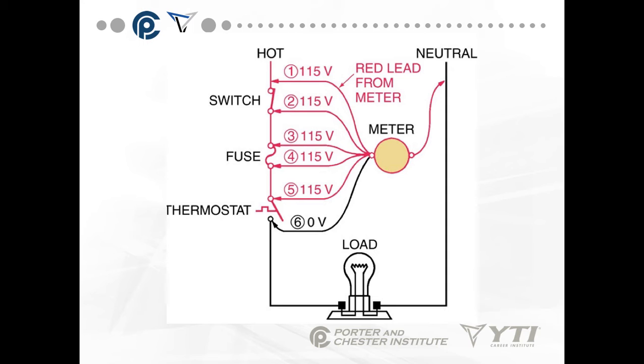We take our meter and use the hopscotch method. We put one lead on neutral and start at point 1. Between 1 and neutral we have 115 volts. Between 2 and neutral, 115 volts. Between 3 and neutral, 115 volts. Between 4 and neutral, 115 volts, because we're going across the load — so that's all good.